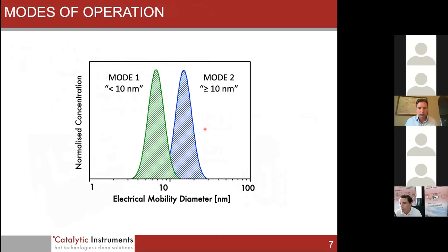There are primarily two modes of operation with the device. Mode one is a smaller less than 10 nanometer GMD aerosol, and mode two is larger than 10 nanometer GMD. If you wanted to measure 10 nanometer aerosol specifically, you might want to use mode two.